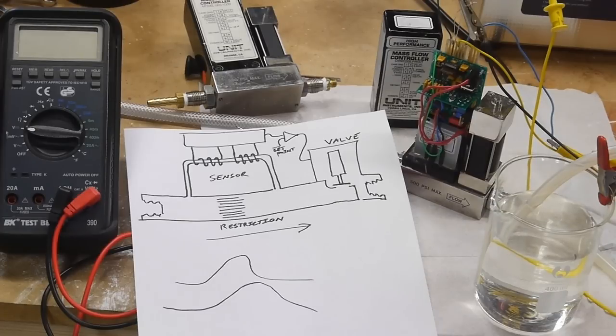As it turns out the correction factor is the square root of the ratio of the pressure differences so in this case we've got about square root 2 since we're running at about 12 psi that's almost 2 atmospheres absolute and that's about 1.4 the square root of 2 and so if we multiply 1.4 by the 3.6 or 7 we get up to about 5 and that makes sense since I set the flow controller to mid scale.